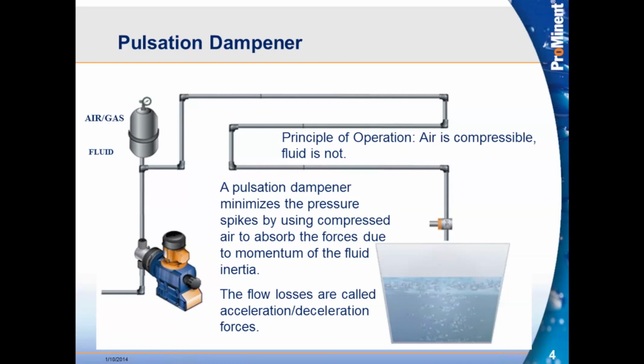We're only stopping the flow between that T and the pulsation dampener. So that amount of volume, that inertia that we have, is very minimal there. So now we're not going to cause the damage inside of the pump. So that is one thing that will help us. It's not always the ultimate answer. We can't solve the world's problems always with a pulsation dampener. But it is one thing that we have to consider. Sometimes we actually have to change the diameter of pipes and whatnot. But with this accessory, it's going to help us by far avoid having to do that. So I think it's a very, very critical accessory for us.